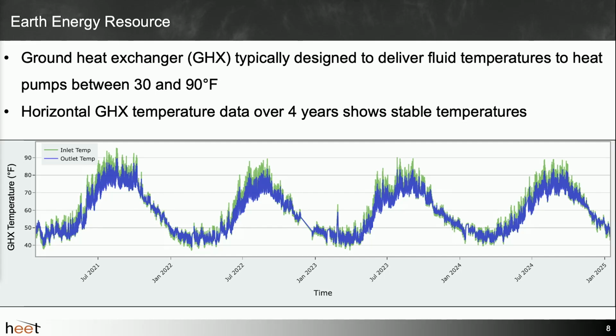So you can imagine that getting your source temperatures from that more extreme air, compared to your ground heat exchanger temperatures, makes the heat pump work harder. Right? It has to work harder to deliver that same amount of heat. So heat pumps like to receive more moderate temperatures so they don't need to work as hard.